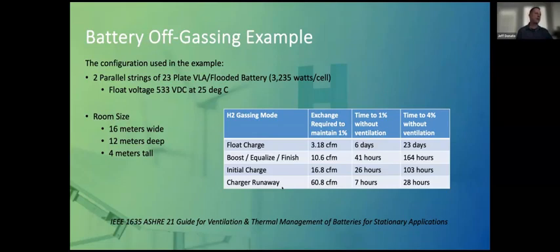Now, in each one of these scenarios, we look at if you remove the ventilation requirement, how long would it take you to reach 1%? And as you can see, things don't happen in minutes or seconds. They pretty much happen in hours or days. And so float charge, as you can see, takes many days. And back to that picture I showed you earlier, that took many days. That wasn't a short event where all of a sudden it developed a lot of hydrogen and blew the roof off the ceiling. That was something that happened over a long period of time.